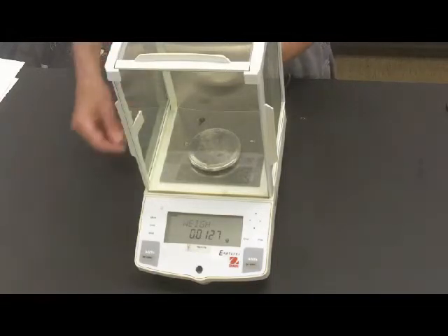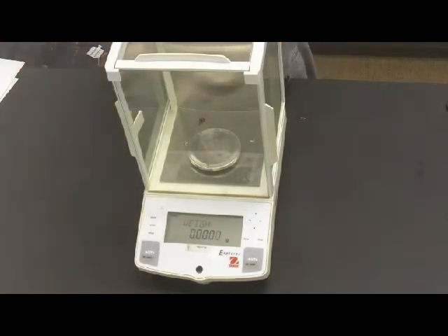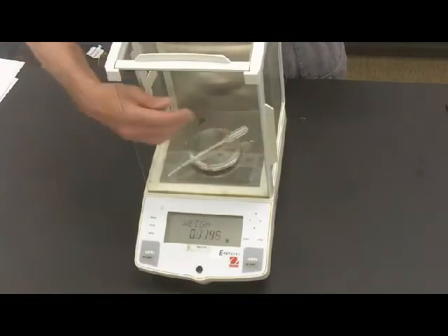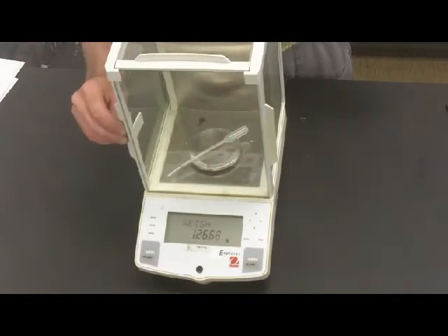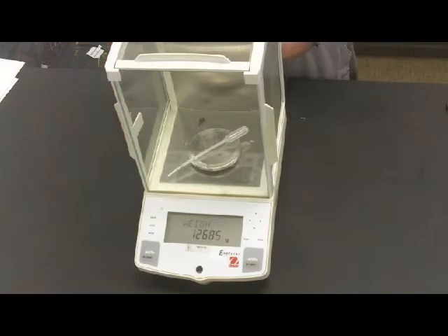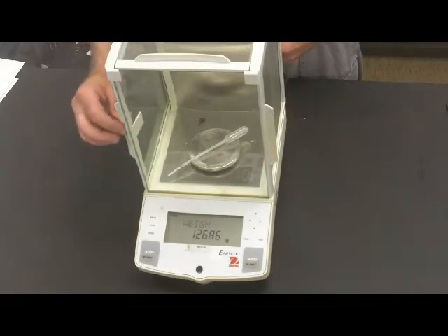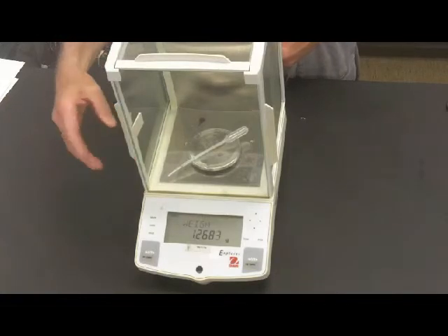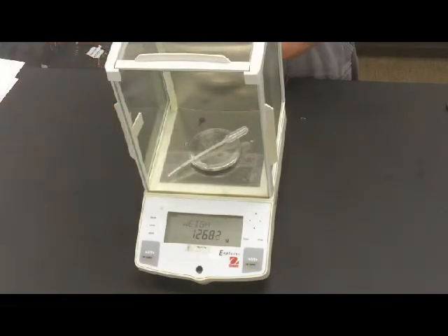When we use this, we can still zero it. Okay. And then if we're going to weigh something, we'll have to open the door to the pan and close it, and then we can read the weight. Now along the way, whether we're zeroing or weighing, we cannot let the doors be open at all. They've got to be closed, because even small air currents are enough to throw off this balance.